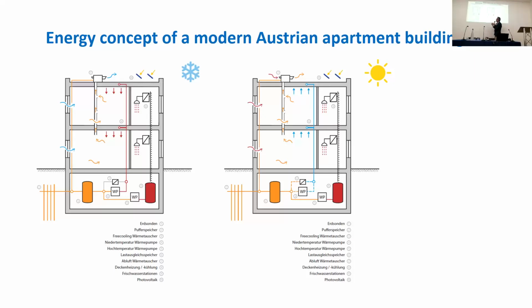And since I said we need recharging of the boreholes, we use as the very simple recharge, in Austria we are forced to have extract ventilation where the air is coming through leakages of the window or through artificial leakages through the windows, and the extract air has been released without use. Now we add a brine to air heat exchanger and use it during the winter already and during the summer even more to recharge our boreholes. So I think this is quite a robust system.